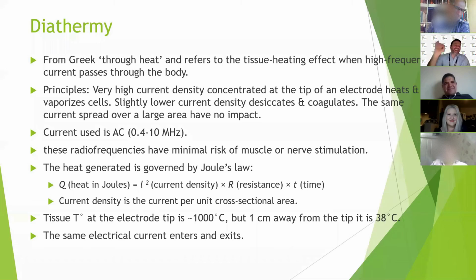The next topic is diathermy. The word diathermy, I tried to find out where it came from, because at some stage I was really interested. It's actually Greek, and it means through heat. Dia means through, passing through. And the reason is the electricity is passing and leaving heat. And that's diathermy. The definition is the tissue heating effect when high frequency current passes through the body. The principle is if you focus a huge amount of electricity into a small area of the body, the amount of heat produced would have an effect on the tissue.